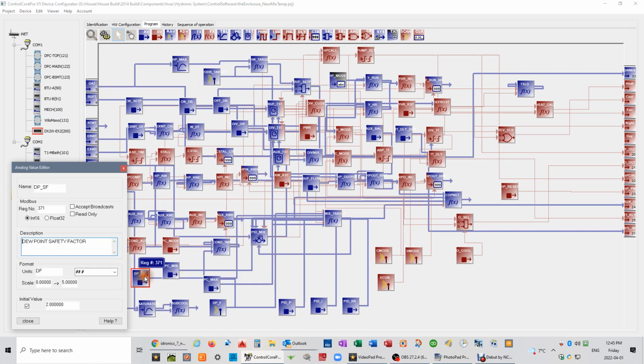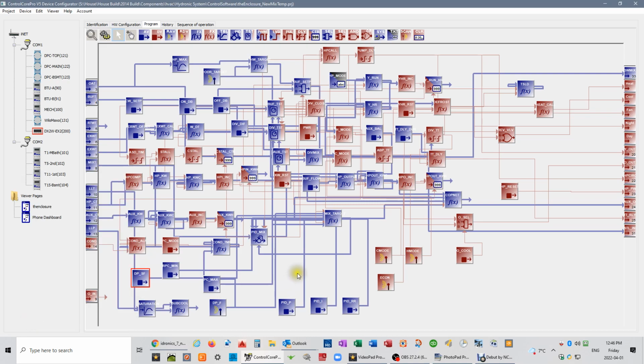And the safety factor can probably be a little bit less because there is a loss of cooling based on the insulation performance of the drywall itself. So the ceiling temperature is always going to be a little bit warmer than the cooled water inside the distribution panel. And all of this is so that we prevent condensation on the ceilings. We don't want the ceilings to be so cold that water is forming on them.